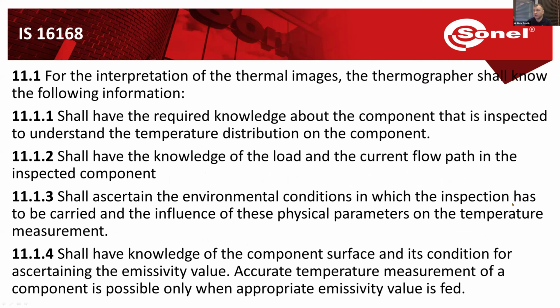The standard says that for interpretation, the thermographer shall know certain information. First, we need knowledge about the component being inspected, and knowledge of the load and current flow in the path of that component. In electrical thermography, it's good if the thermographer is also an electrician who understands what we're checking and what the hotspots mean, because we could have a skilled thermal imaging technician who finds a hotspot but doesn't really know how it influences the electrical system. That's why some electrical knowledge is needed.